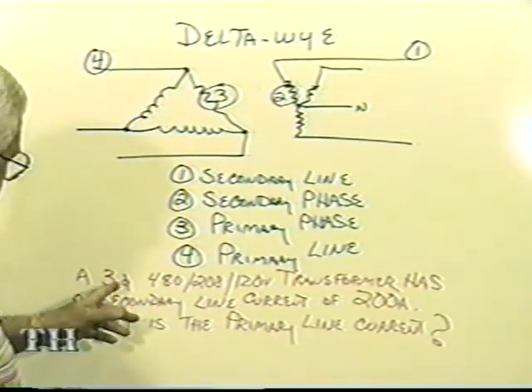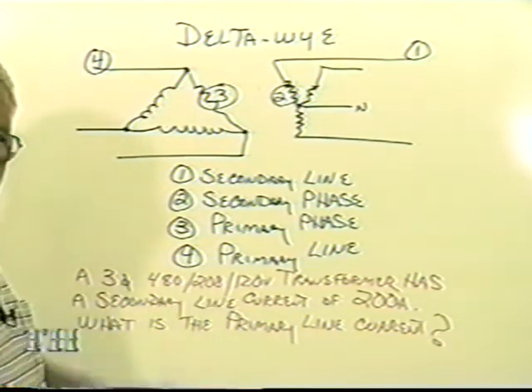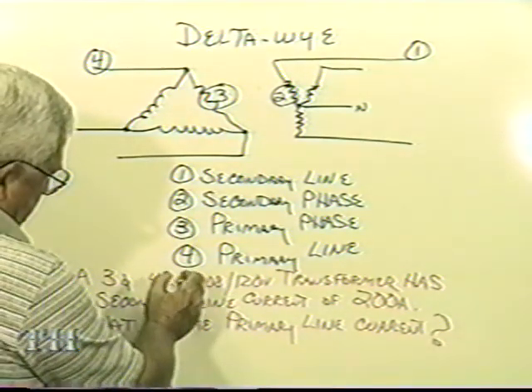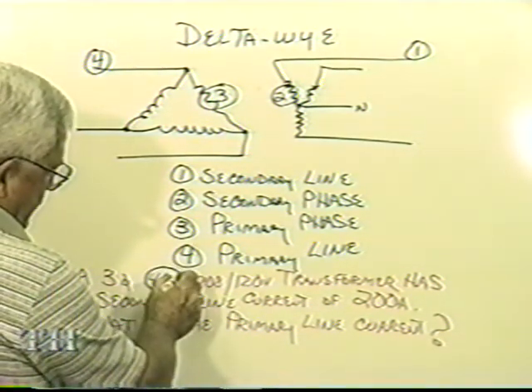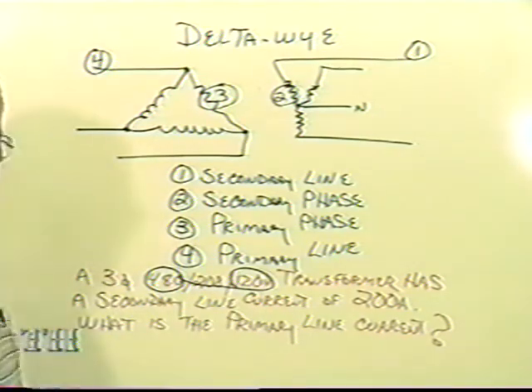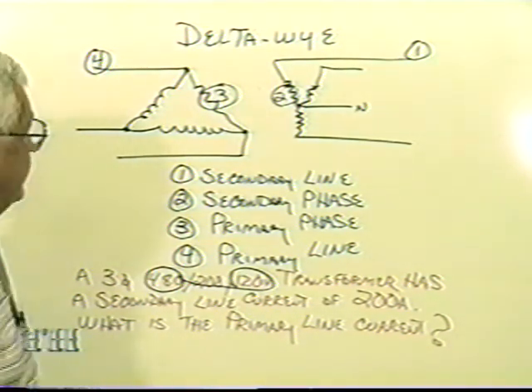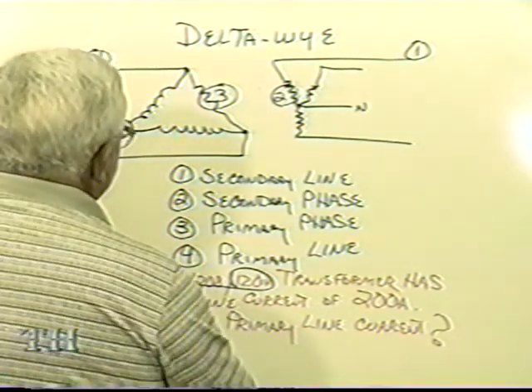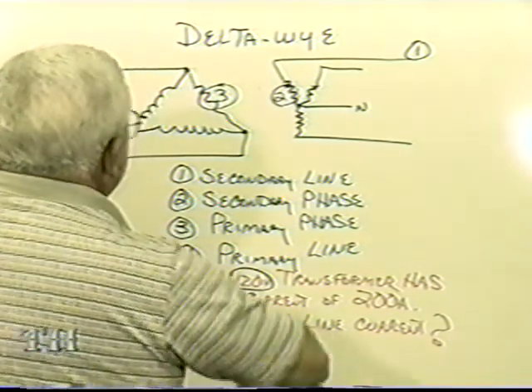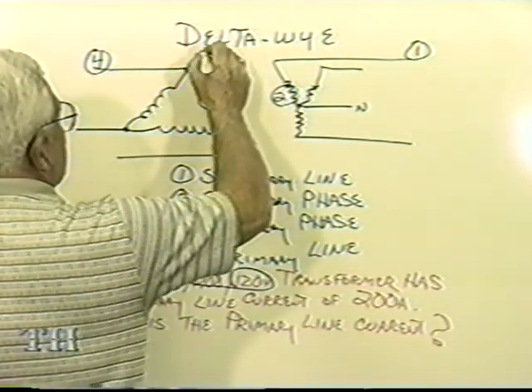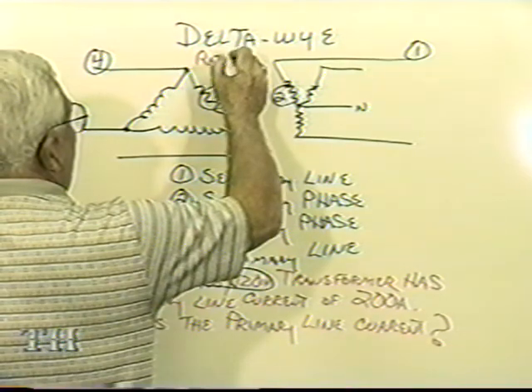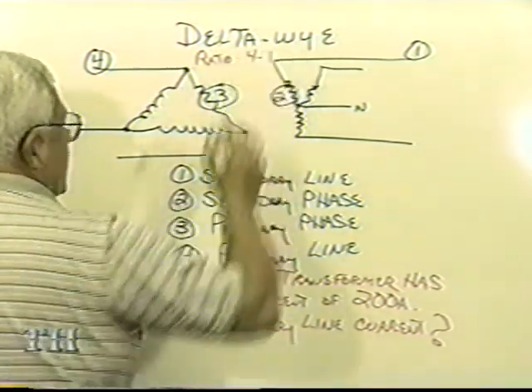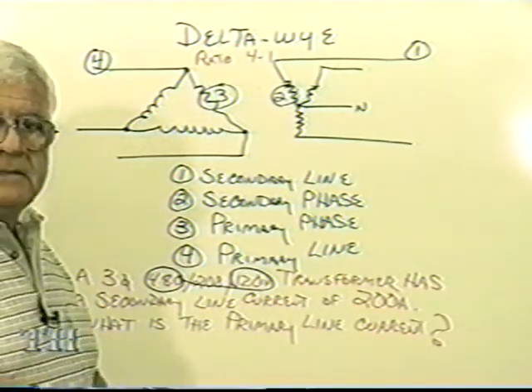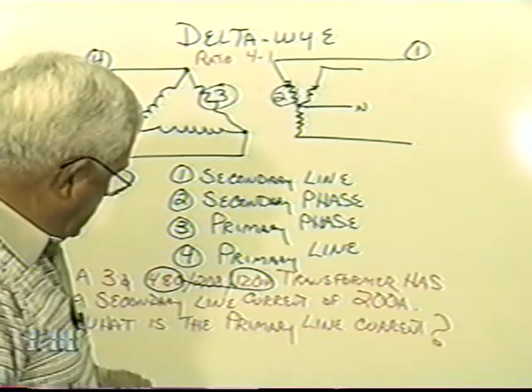In other words, they're saying 480, 208, 120. We just learned a moment ago that the ratio is 480 to 120 volts. That's called phase to phase. So right up here, I'm going to write the ratio: 4 to 1. Okay? And we learned how we determine that.